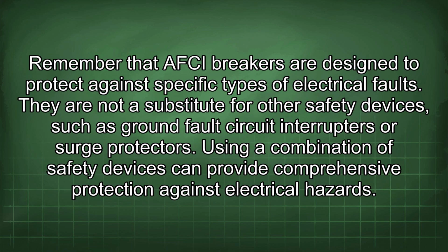Remember that AFCI breakers are designed to protect against specific types of electrical faults. They are not a substitute for other safety devices, such as ground fault circuit interrupters or surge protectors. Using a combination of safety devices can provide comprehensive protection against electrical hazards.